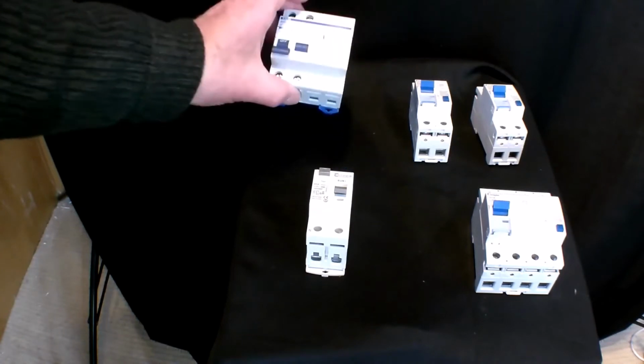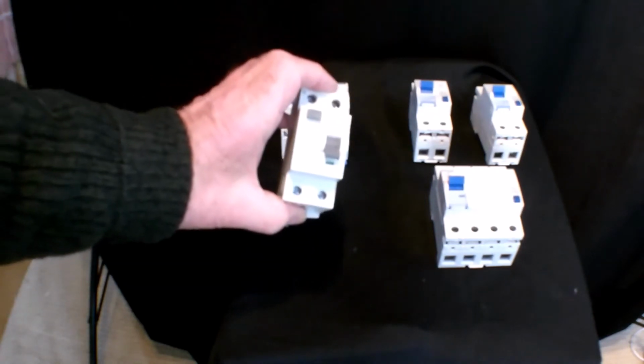Here I would like to show you some of the RCDs that are available. Single phase and three phase units are the same size if you're using a type B. If you're using a type A, F or AC, the single phase ones are in the conventional 2 module size.